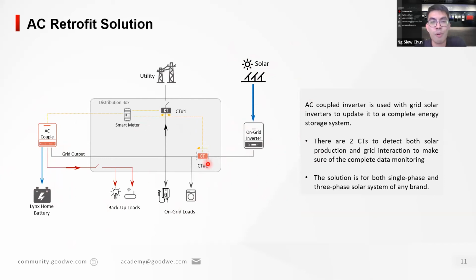We add additional CTs here to read the power generation from the grid-connected inverter, whichever brand it is — it could be GoodWe or another third-party brand. We read that and feed it back to our smart meter, and the energy management system algorithm incorporated into our AC couple inverter takes care of all the controls.